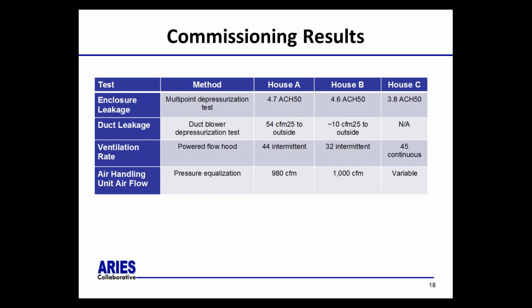Someone was asking, it was somewhat surprising that House C did not have a much lower heating energy use. Do you have any theories why? The primary theory is that the mini-split COP was not what was expected; it was about the same as the traditional heat pump. That, plus the addition of resistance heat, brought the heating energy for House C up to about the same level. Also, we had about 3 times the ventilation in House C, which puts an additional load on the heating system—better air exchange, but more electrical energy use. And as Jordan indicates, if the COP gets back up to what we expect with proper adjustments, we would then expect to see heating side savings.